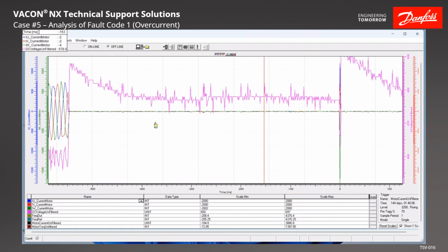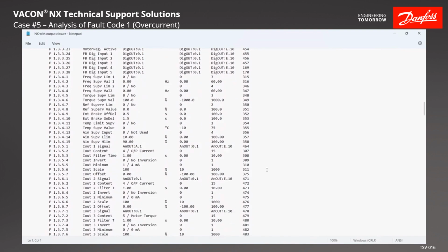The other possibility is a contactor dropping out and pulling back in. Now that could happen in that shorter period of time. Again, a little bit questionable, but it could happen in that shorter period of time. So if there are contactors out there, then you've got to somewhat eliminate the contactor. Bypass the contactor, depending upon how short a period of time it is in between the trips.